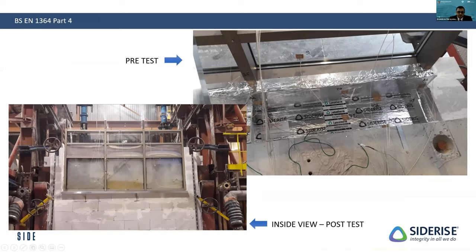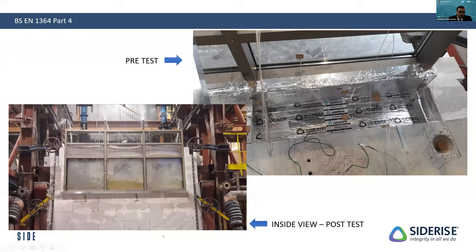It is important to know that you test for the void size and get a listing. We have seen engineering judgments that allow testing for a 100mm gap and extrapolating to 200 or 300mm. However, an approach where you test for the largest gap should be adopted, so you have evidence of performance rather than relying on a desktop study. Use a system or listing as close as possible to your application, and do not mix multiple listings.